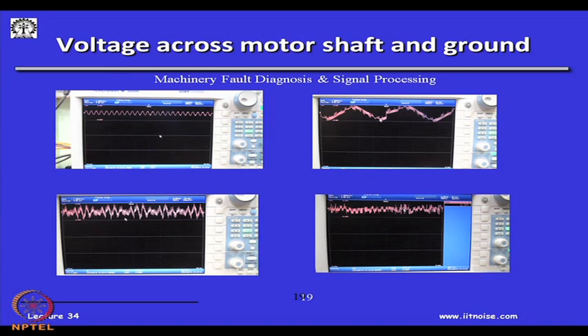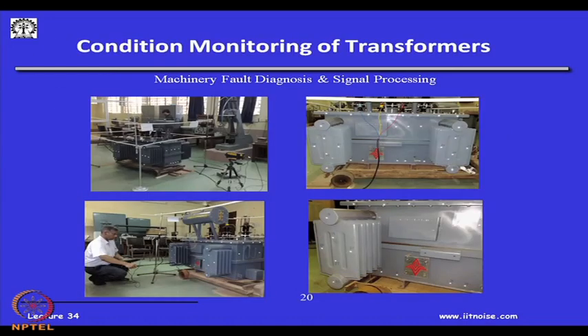So motor faults can be detected through these techniques which we discussed, mostly through signature analysis, though you can also do vibration monitoring of electrical motors. And then, how do you monitor the condition of transformers? Basically, a transformer is nothing but a core with a coil, and this coil is kept in a tank full of oil, and this oil is to be maintained at a particular height. Because of the eddy current losses etcetera, this current generates heat.